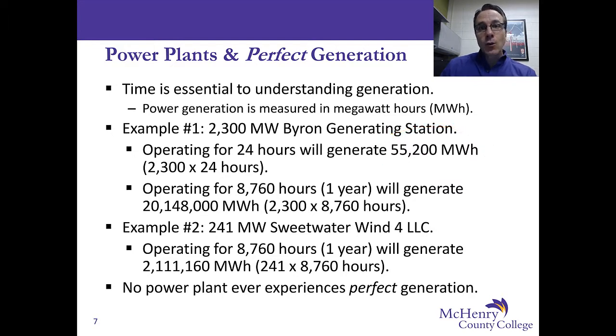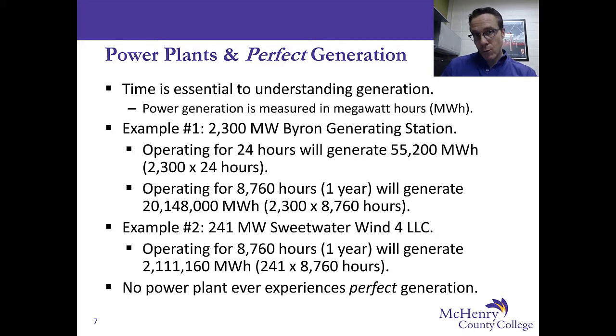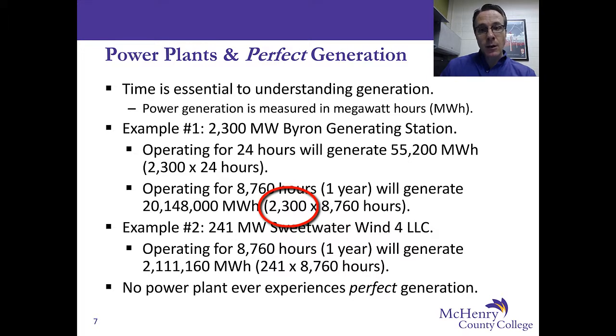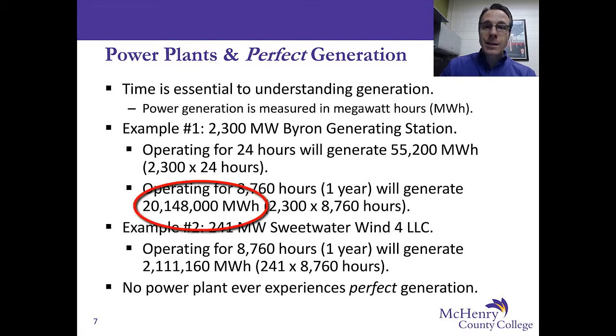We can extend this 24-hour day out over an entire year using the same procedure. Instead of using 24 hours — the number of hours in a day — we use 8,760 hours, which is the number of hours in a year. Running the Byron Generating Station at 100% for an entire year gives us a generation of 20,148,000 megawatt hours.